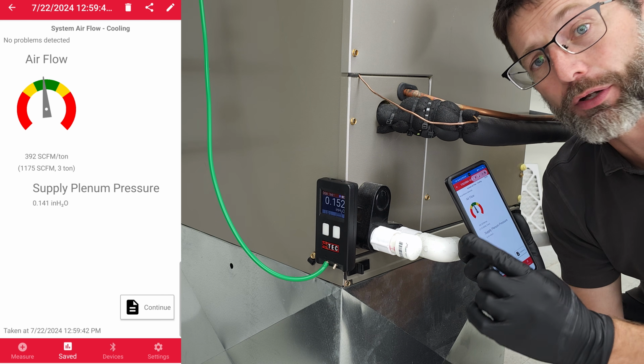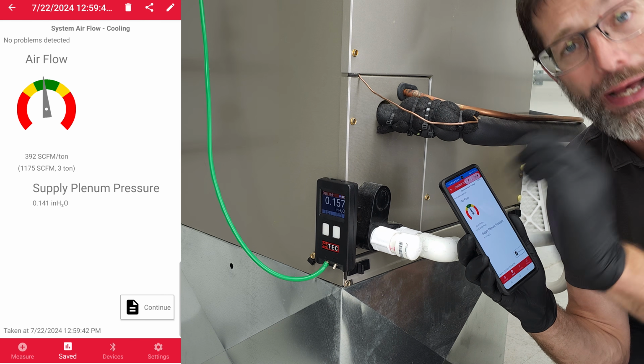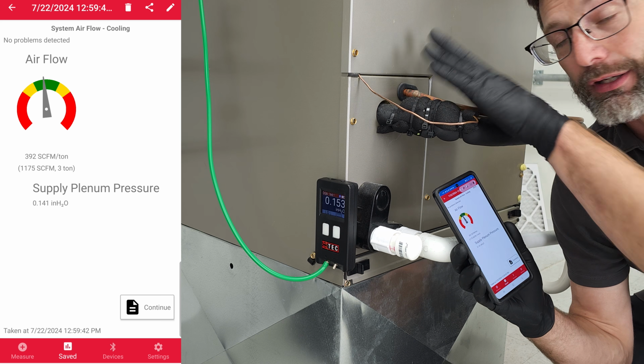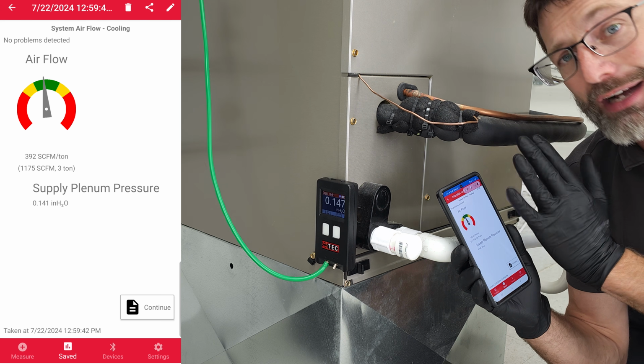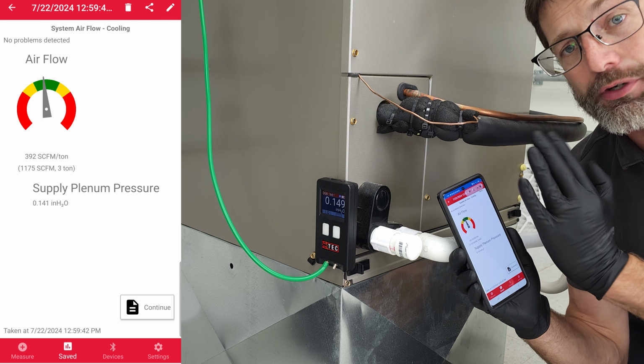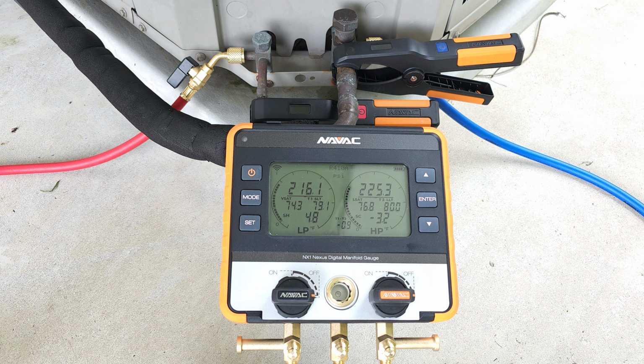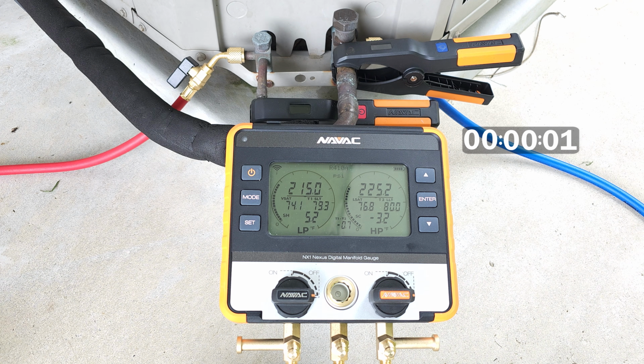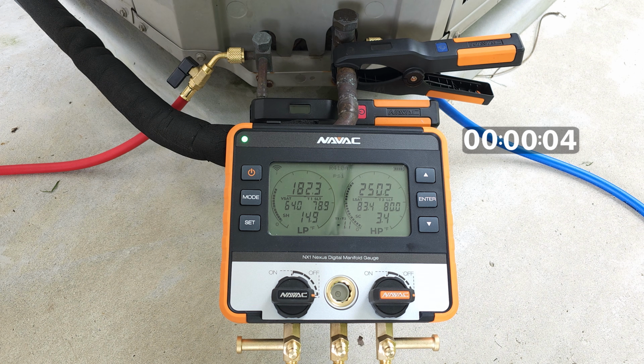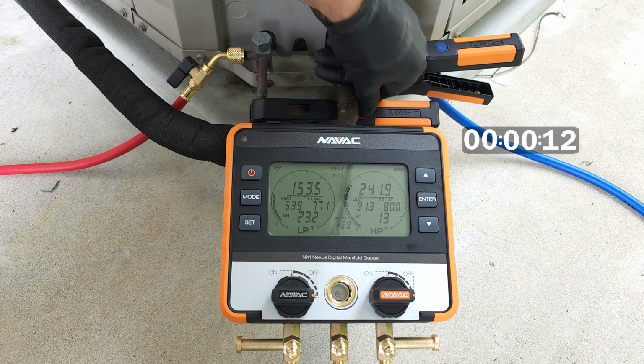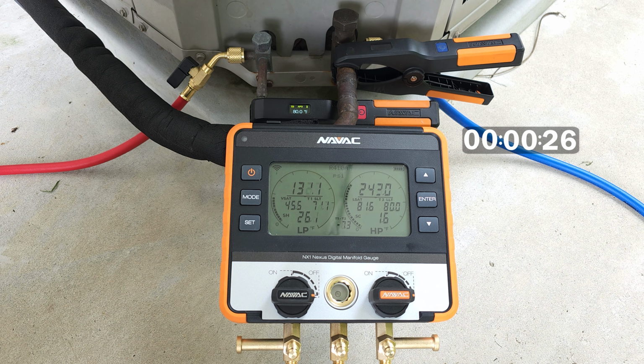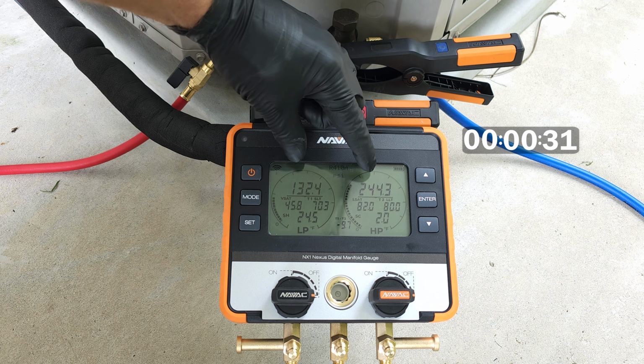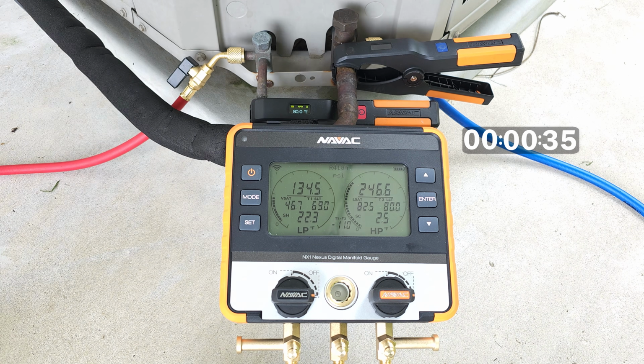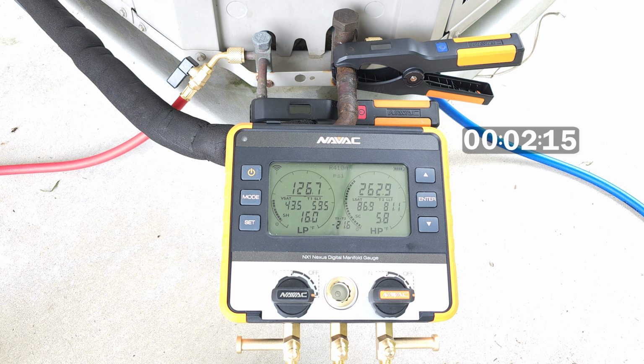Since our airflow is good, what I'm going to do is I'm going to turn the power off to this air handler. I'm going to put back in the filter, and then I'm going to turn both this air handler on and the outdoor unit. I'm going to wait about 5 to 7 minutes before measuring our pressure, saturated temperature, superheat, and subcooling. Now we're going to turn the outdoor unit back on. Let's give it about 7 minutes or so. So anywhere between 5 to 10 minutes, and then we'll check our pressure, saturated temperature, superheat, and subcooling.